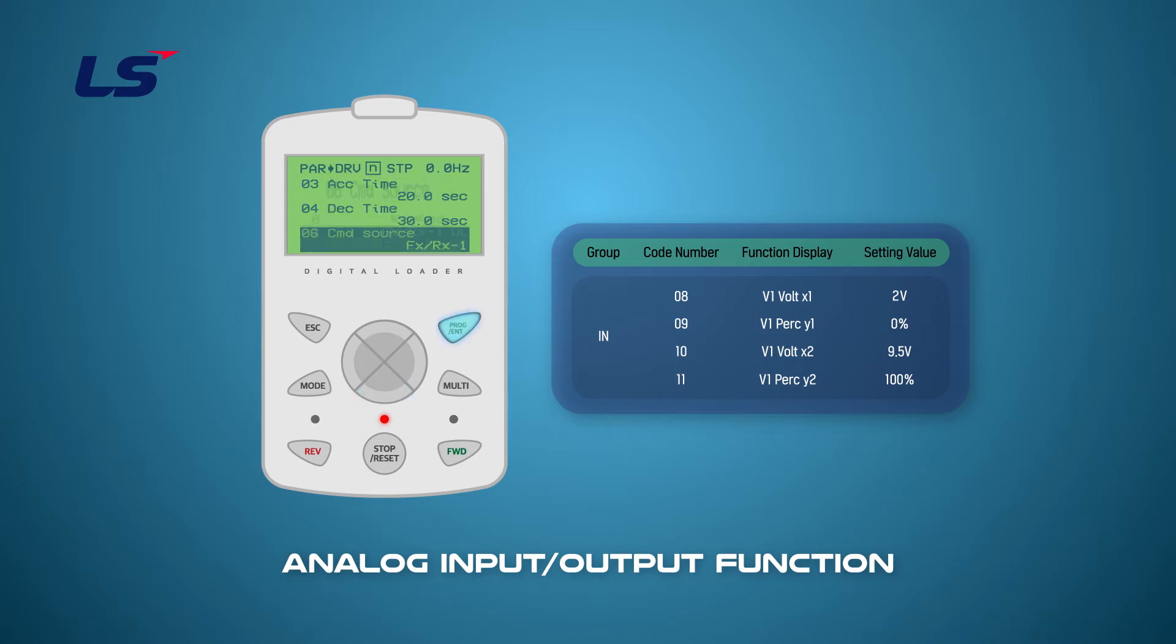Set to FX RX1 at DRV6 and set to V1 at 7 before moving to IN-group using the direction key. Set the minimum input voltage at IN-group 8 to 2 volts and the corresponding input level to 0% at IN-group 9.